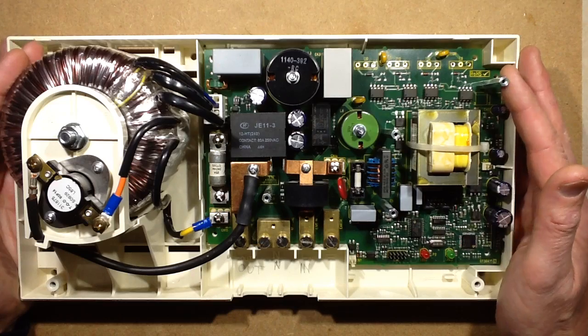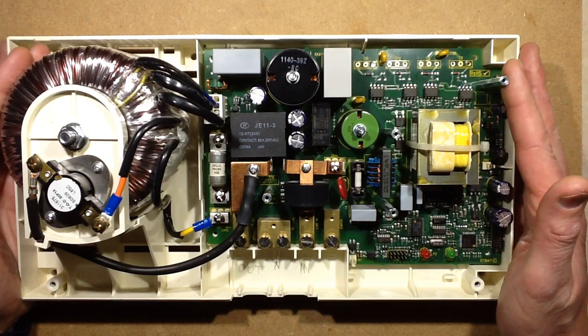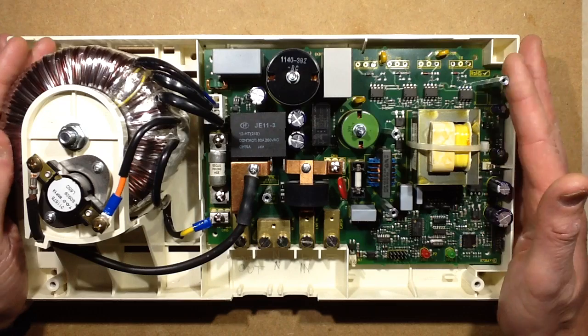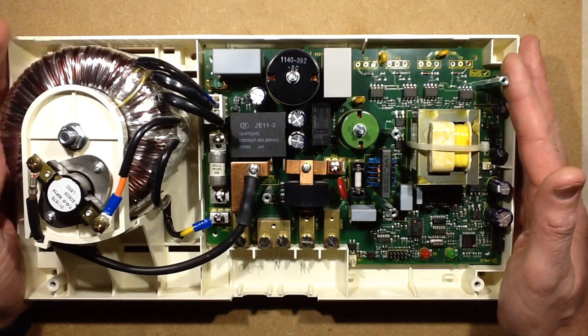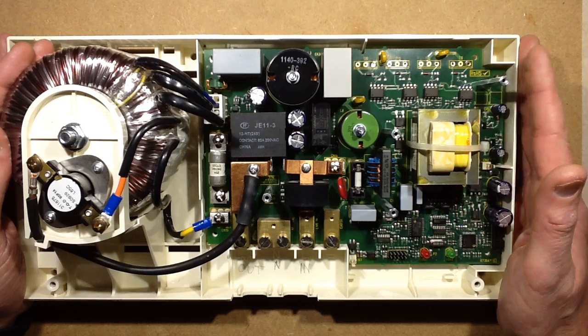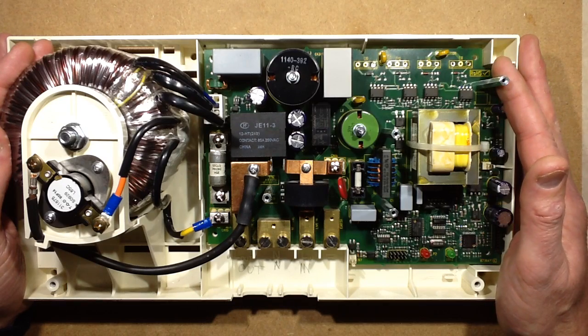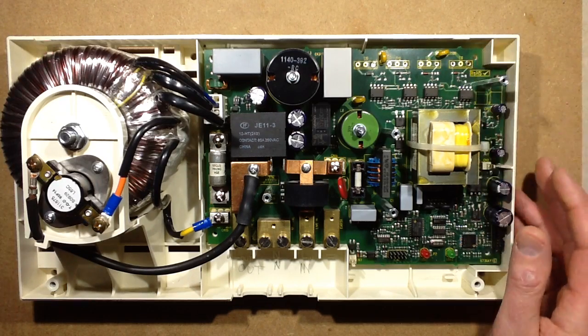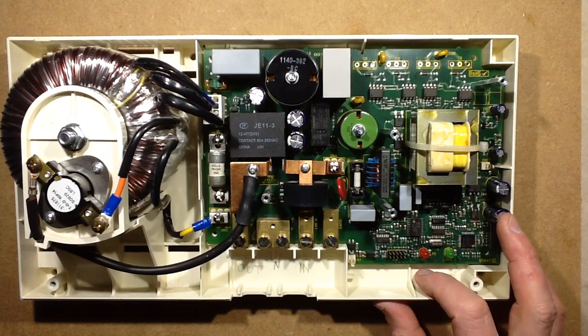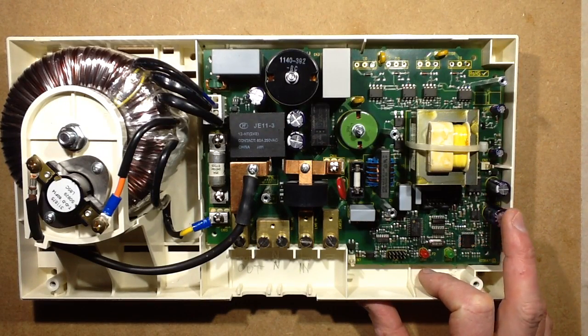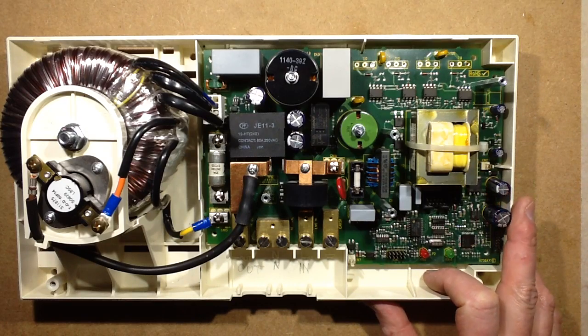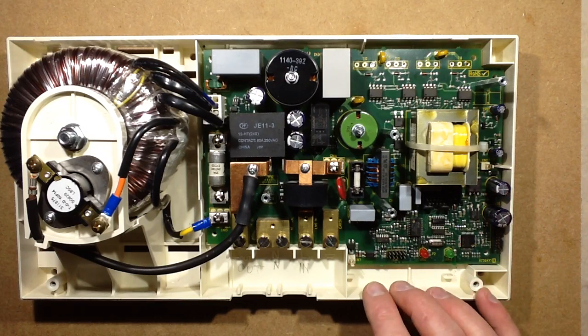I think they might just have picked the best results, because I don't see in a modern installation this unit actually doing anything other than using a bit of power, not saving a lot, compromising things, making things run a little bit longer than they would have normally. I'm guessing fridges would also have to run a bit longer to achieve the same temperature if the compressor is being driven at a lower voltage. So it's interesting. It's an intriguing device, but to be honest, I think this is in the category of snake oil.